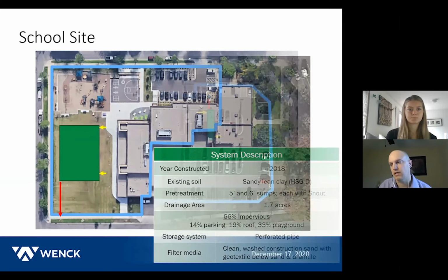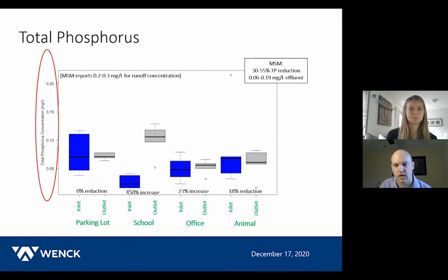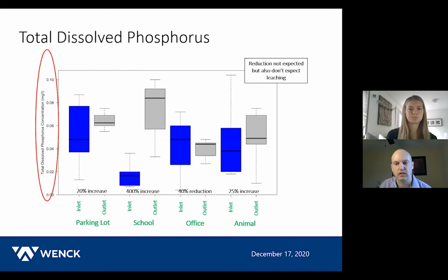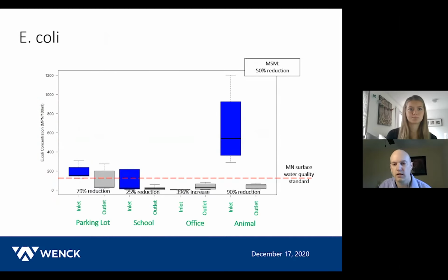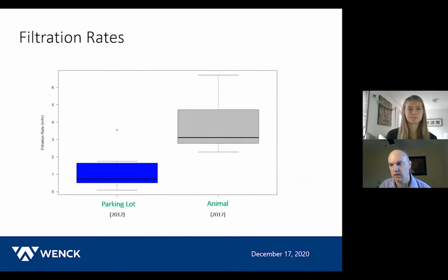Now, in terms of design, it's probably not reasonable to take that storage into account as we design these systems, because again, if you think back to the beginning slides, our intent here is to clog these filters. We want material to build up in the sand. So I don't think we should be depending on that to store water and slow it down.